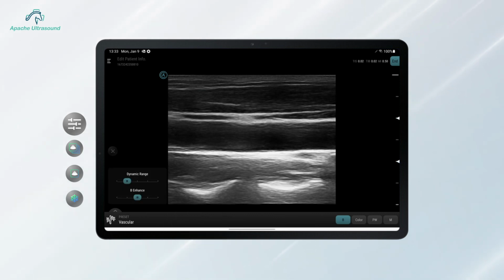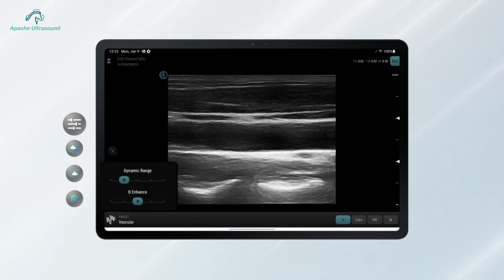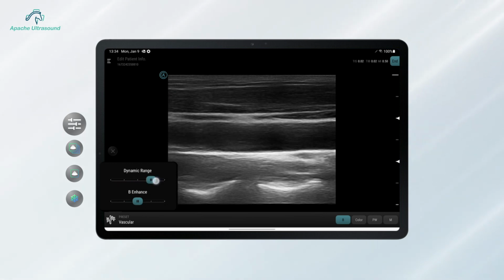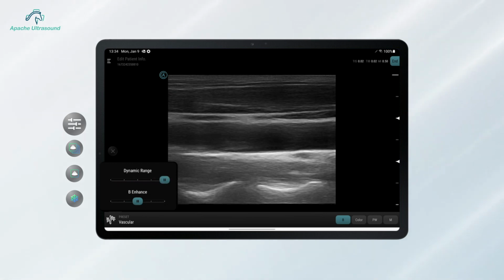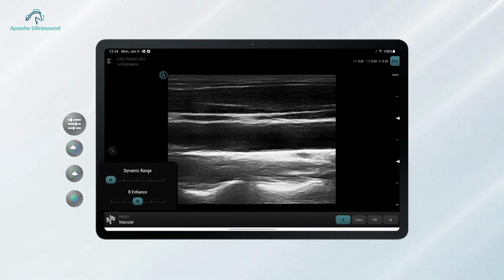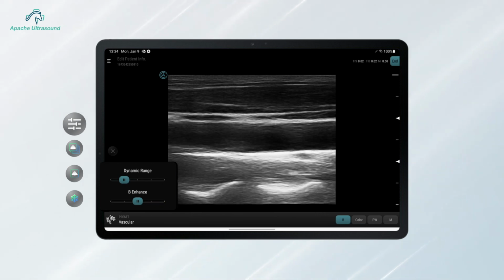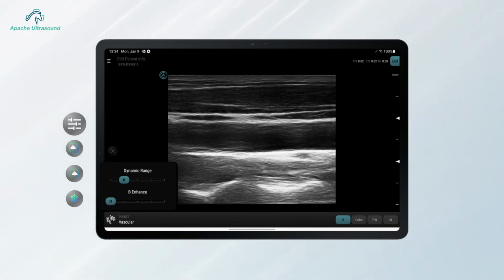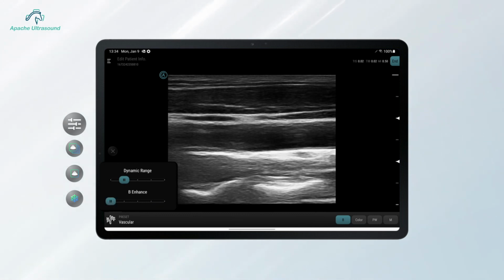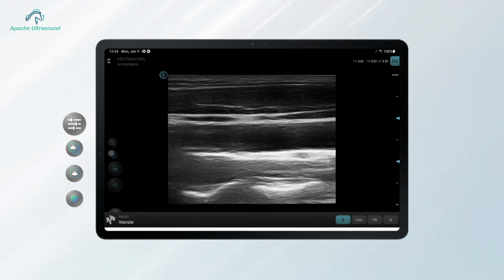There is a fan setting where you can adjust the dynamic range and B enhance. As for dynamic range, there are 5 bars. Adjust to the right will increase the grayscale levels in your image, and adjust to the left will increase the contrast in your image. As for B enhance, by adjusting to the right will give you a smoother image, and by adjusting to the left will increase the speckle size in your image.